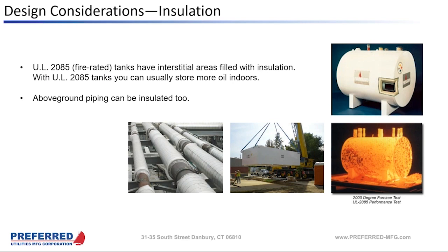Our goal is really to maintain fuel at temperature. It's not to necessarily add BTUs to a tank or to even try to elevate the temperature that much. The amount of BTUs you can add with heat trace and with insulation is very limited. So what we want to make sure in our design is that the fuel that we're putting into that insulated piping is already at a spec temperature, and that we're not trying to either elevate the temperature of that fuel or trying to elevate the temperature of the fuel of the tank that's going into. We're really just maintaining it along that route.